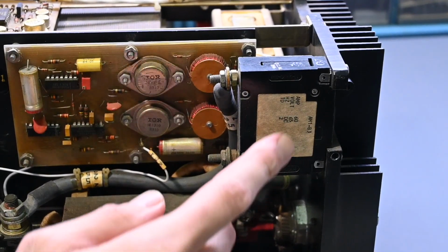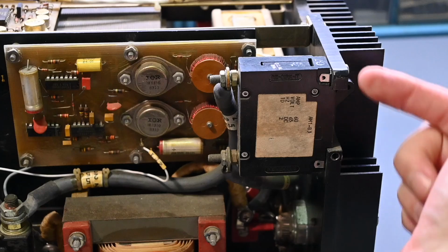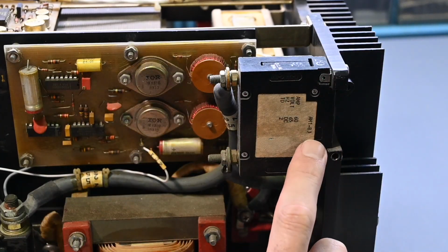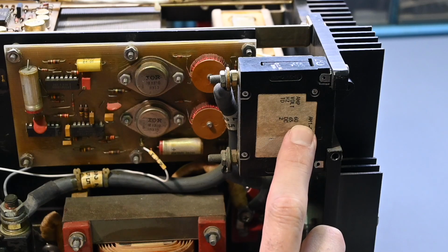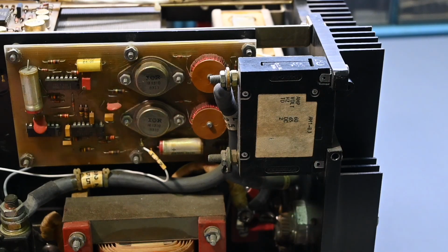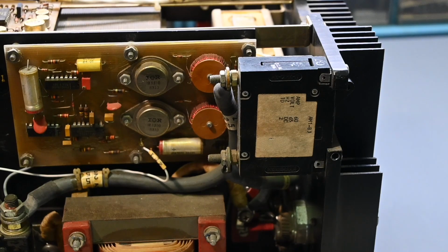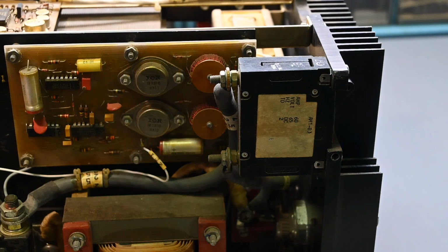And actually it looks like over here, get you moved up over to this side. So here's the circuit breaker that's on the back panel that reached through when the cover is on. You couldn't see the side right here. And this amp rating right here, it says 60 amp on the breaker. So that makes sense. If this is rated 50 amp and then just a little bit over that, then it trips the breaker. So that gives us an idea that when this is under full load, the current draw is going to be pretty much topping out at about 50 amps or so.